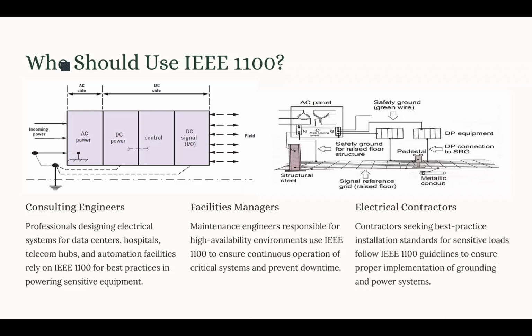Now, facility managers can also use this standard. Basically, they are responsible for the ongoing operation of the power and grounding infrastructure. So this IEEE 1100 helps them detect and mitigate issues proactively, before they cause system failure. One responsibility covered in IEEE 1100 is monitoring grounding impedance and common mode voltage. They have to make sure their target grounding impedance is always less than 1 ohm and maintain a uniform signal reference. And they have to keep the common mode voltage under 1 volt RMS so they can prevent logic malfunction.